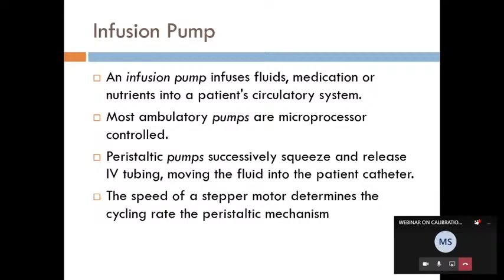The speed of a stepper motor determines the cycling rate. How many ml of drug volume is delivered is based on the speed. With the help of the motor, speed is measured accordingly, and it is correlated with the volume. Volume is calculated based upon the stepper motor rotation. It is a computer controlled microprocessor device. With the help of motor speed, the machine measures the volume. This pump can be calibrated with the help of a calibrating analyzer.